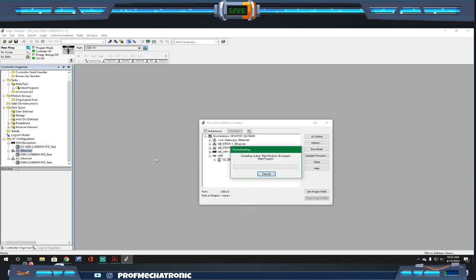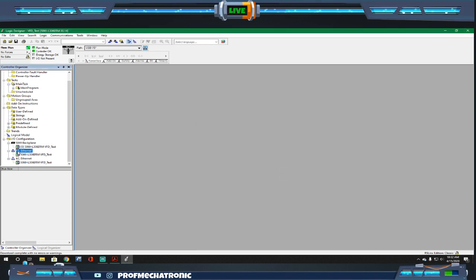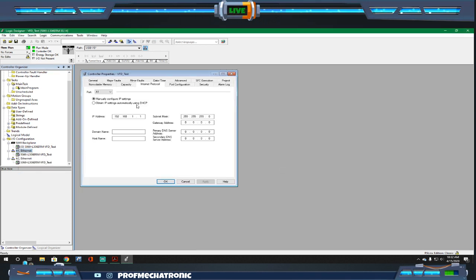So once we download this current VFD program, we will actually be able to set up our Ethernet IP. We'll put it back into run mode. All right, so now we can set up our Ethernet IP settings.